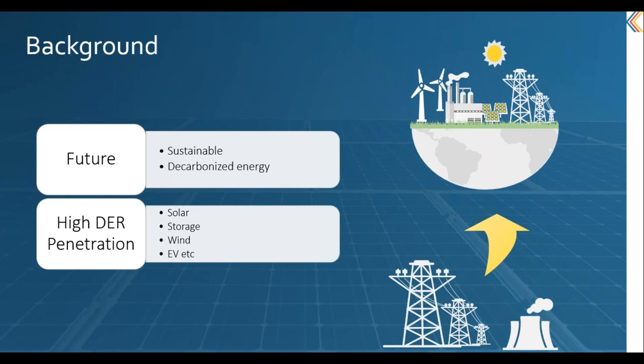However, decentralizing the electricity grid introduces a lot of new instabilities in the grid. For example, with the conventional approach, whenever a local fault, a voltage spike, or any other disturbance happens in the grid, protective circuitry quickly shuts down all the energy sources to isolate the fault. However, this will lead to cascading system-wide instabilities on a system with high intensity of DER. So it's important for DER plants to automatically ride through these disturbances rather than simply shutting down.